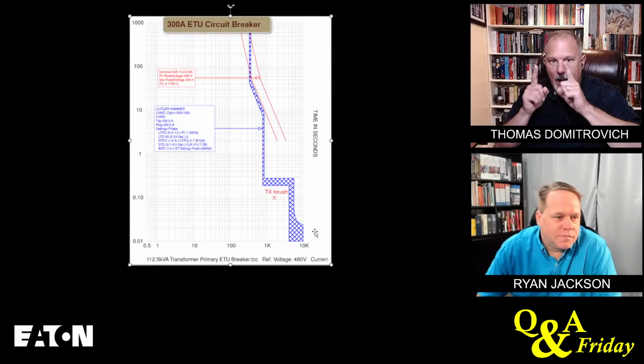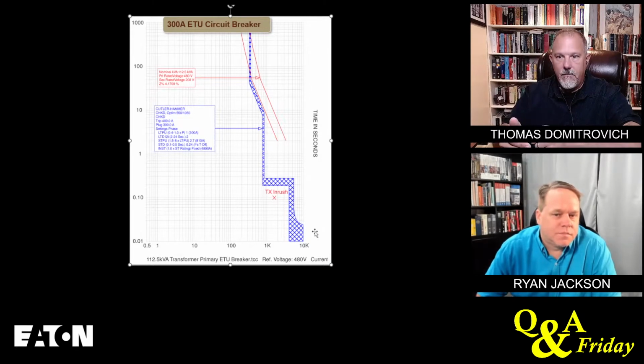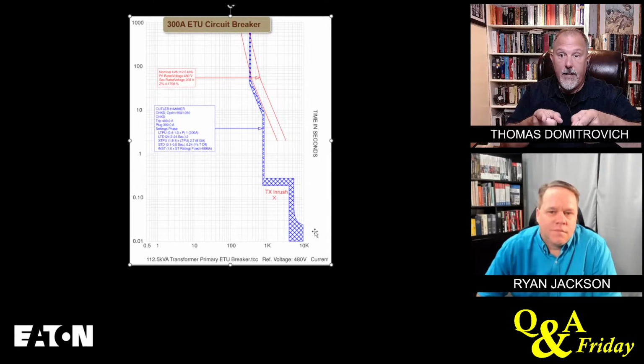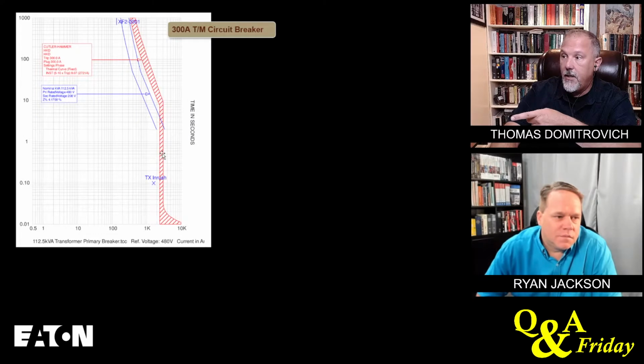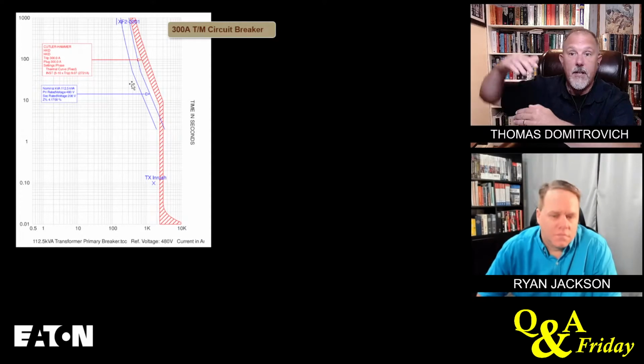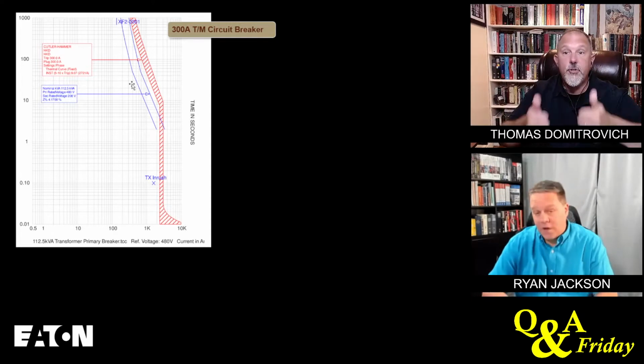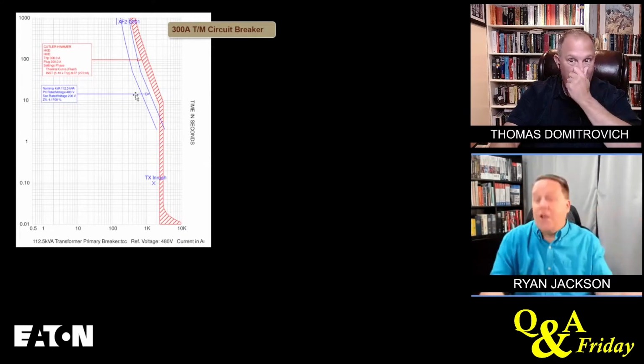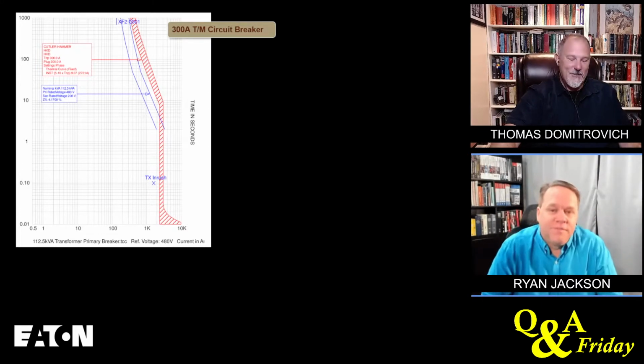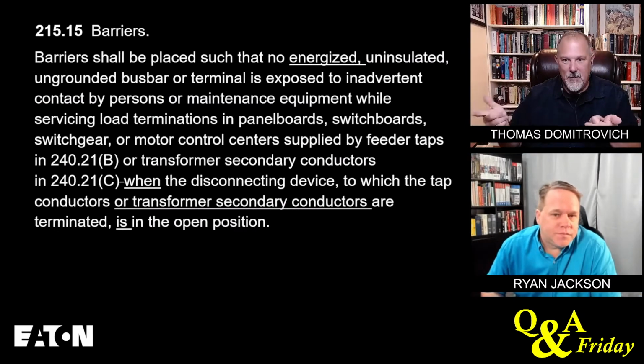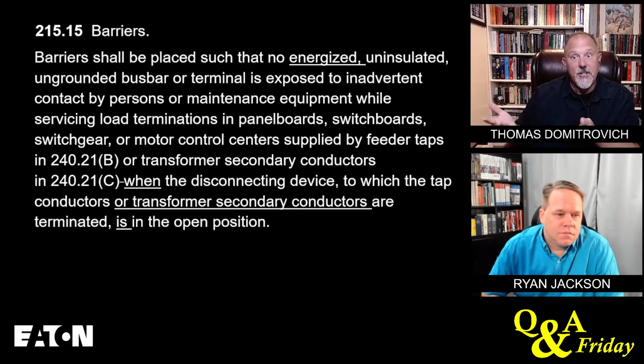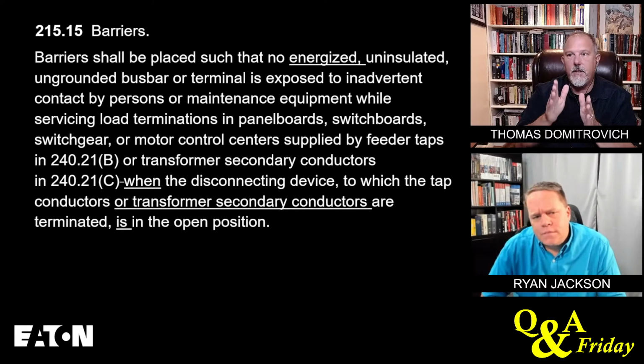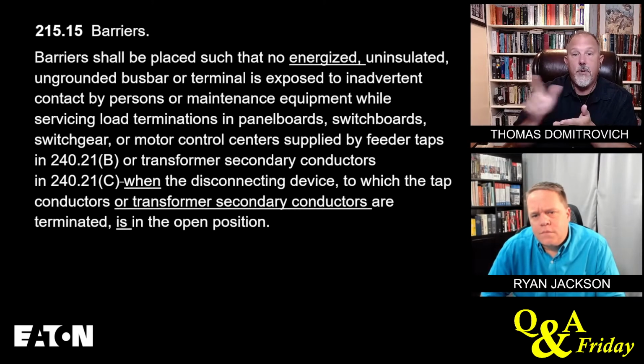I am providing an intentional delay of the primary overcurrent protective device instantaneous, right? This one here has a short time delay, but I could put a circuit breaker that doesn't have a short time delay, and my clearing time for a fault on the secondary is going to be cleared by the primary's overload region, which is going to produce a high incident energy, a long duration, because that yields high incident energy. So that's why I went to this language and said we need to put transformer secondary conductors in there. Because of the controversy, even though it seemed like a simple change to me, I did not put that in my TIA. I think that's going to be for a 2026 cycle, because the hazard is exactly the same that we're trying to mitigate with that barrier.